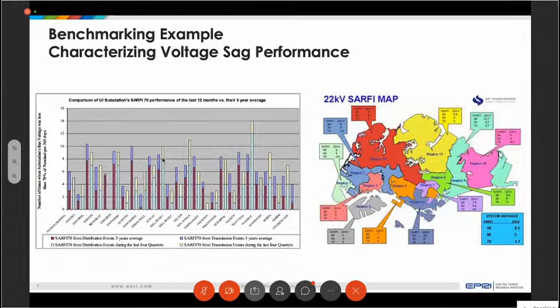And it's dependent on a power quality monitoring system that they have in Singapore, with power quality monitors all over the distribution system that are continuously recording these events. So those are benchmarking examples. As we integrate power quality monitoring with operations and use it to identify problems and solve those problems, we can really increase the value of power quality monitoring. These are a couple examples that I always like to use.